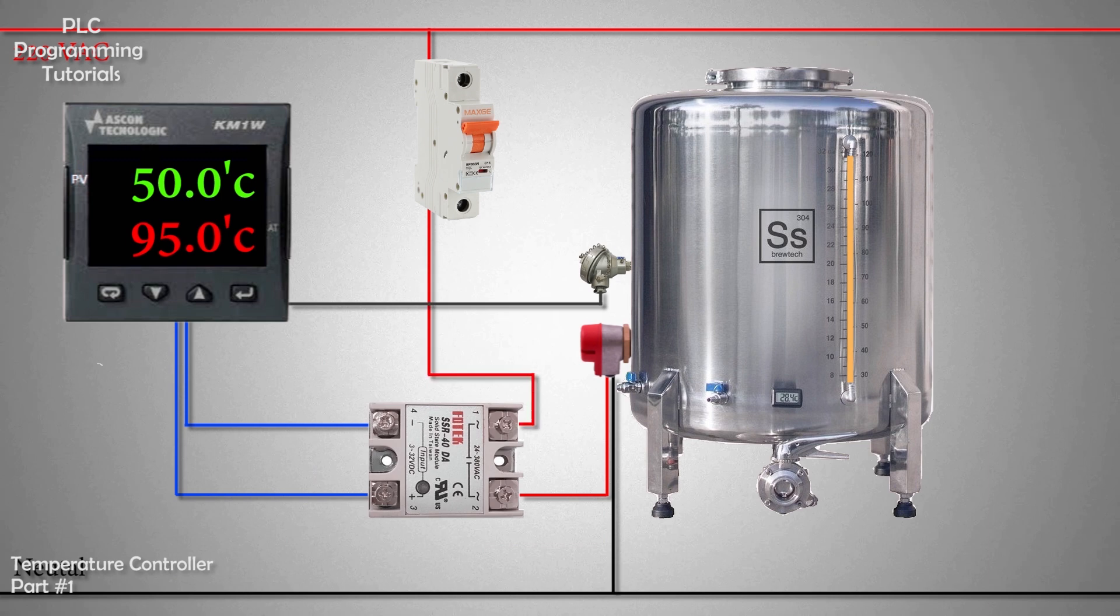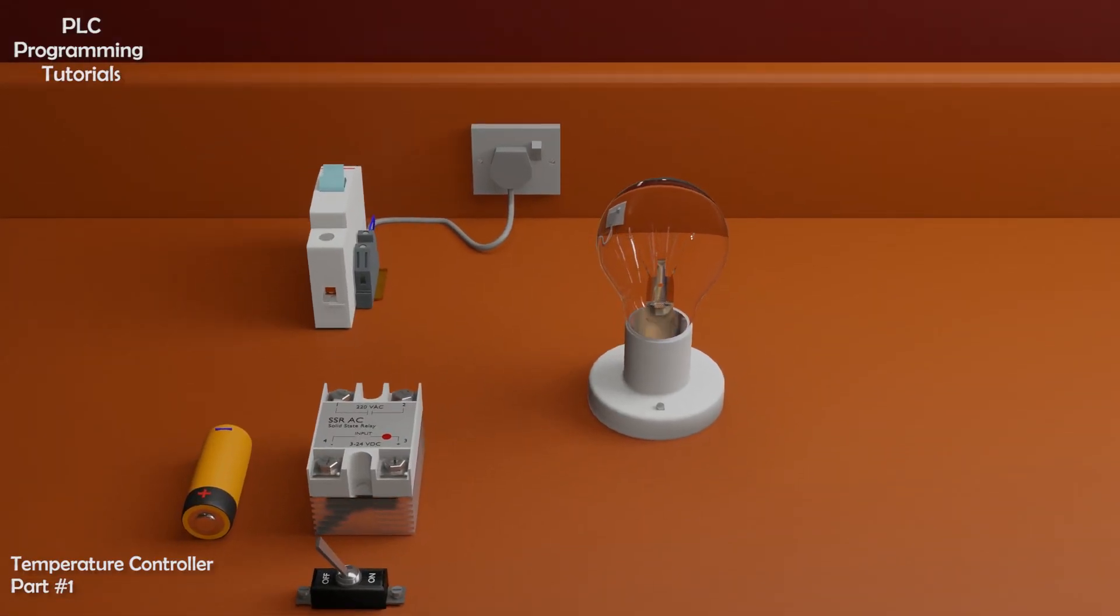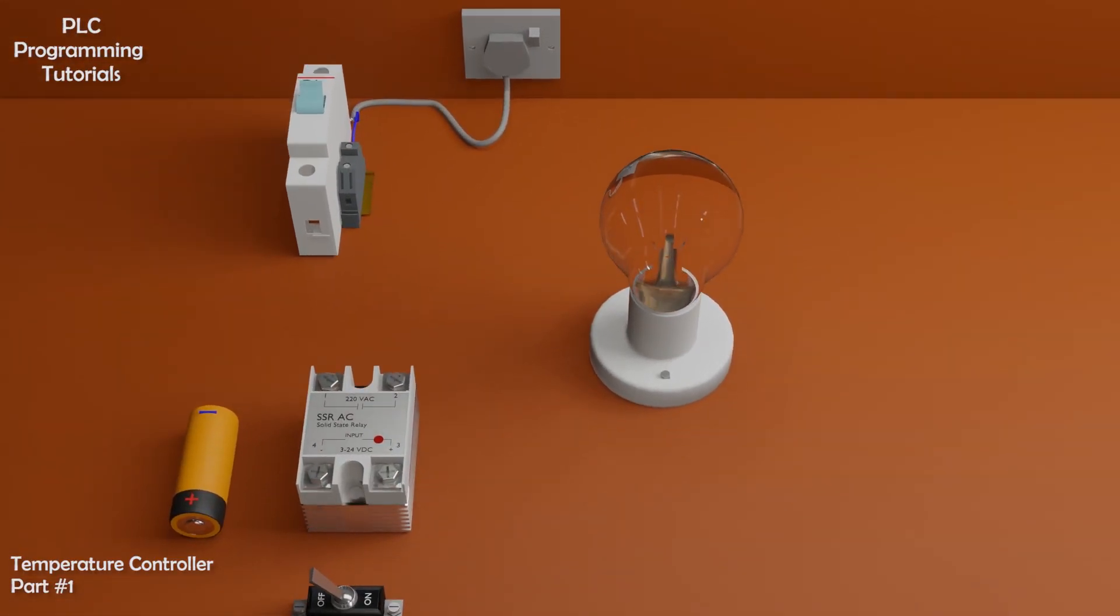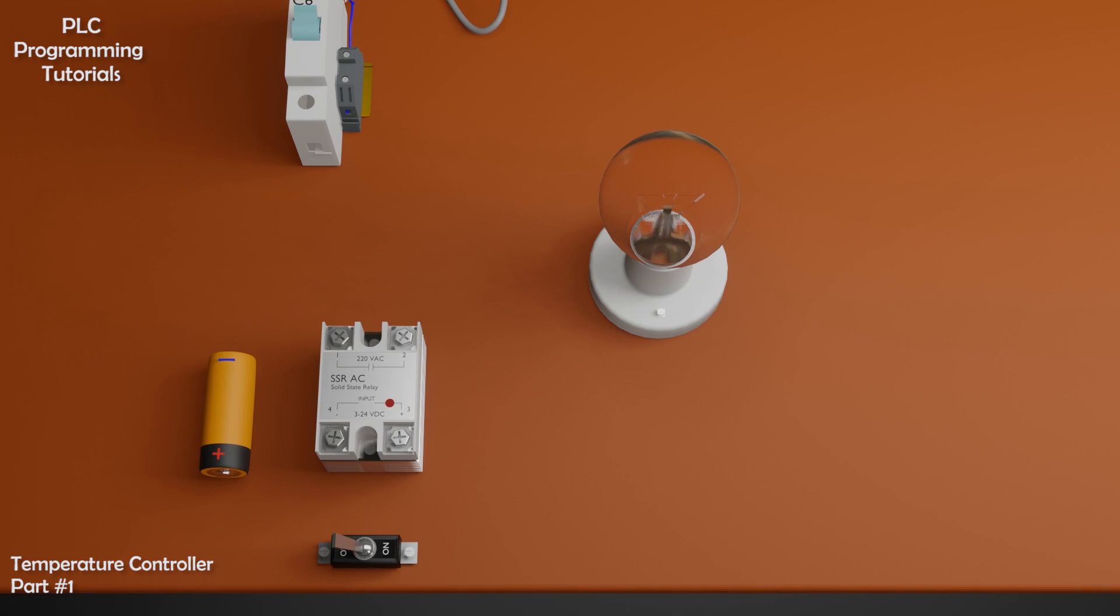Let's see now how does SSR relay work. As you can see, the SSR relay has four terminals. Terminals 1 and 2 are the load contacts of the SSR. Load is connected in series with these contacts. When this SSR relay turns on, these load contacts conduct the electric current and supply this current to the bulb.